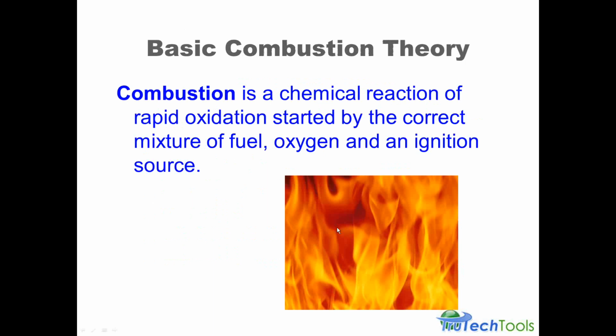So, basic combustion theory, let's get into it. Real simple definition here: combustion is a chemical reaction. So we will be talking a little bit about chemistry, not at a very advanced level, because that's basically what combustion is, a chemical process. It's actually a rapid oxidation, which is the mixing of fuel, oxygen, and a source of ignition to release the excess heat that's trapped inside the fuel itself. In order to make this happen, we have to have three things come together, sometimes called the combustion triangle: fuel, oxygen, and a source of ignition. They have to be in the correct ratios, but usually this is what the manufacturer is providing in the appliance. Those are the three main things required.